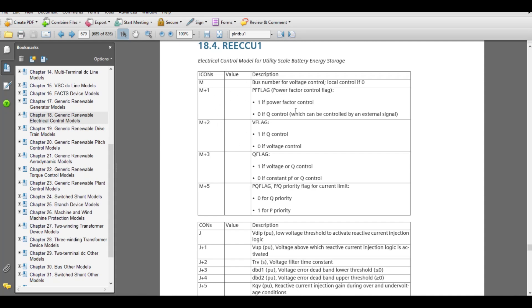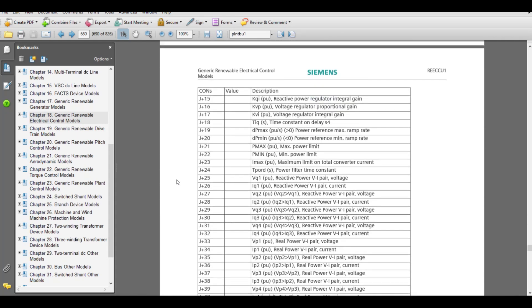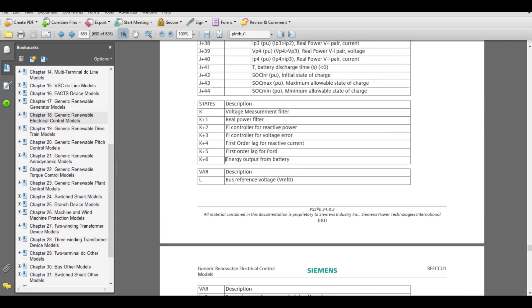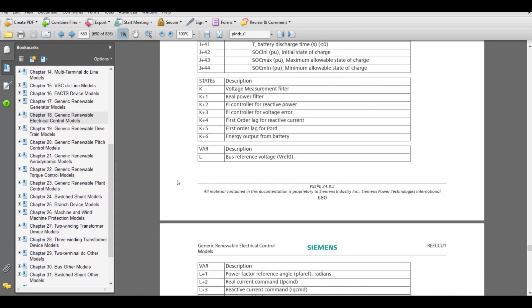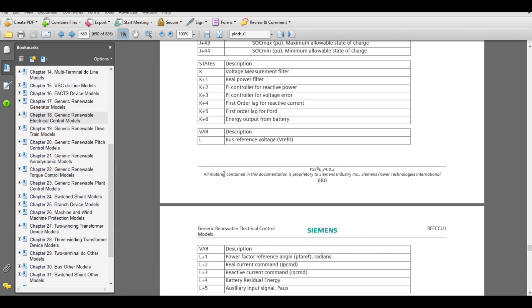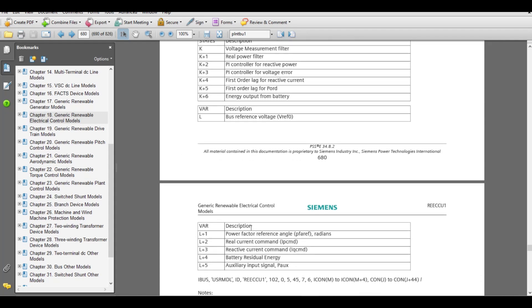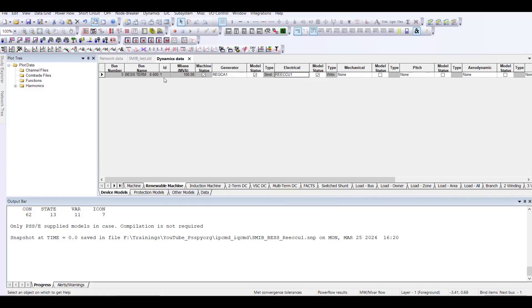If you go into that PDF file, you are going to find the model details — what kind of data you need to provide for the ICONs, similarly for the CONs, the states, and the vars. In PSSE, you can plot these states as well as vars. My area of interest is ipcmd and iqcmd, which correspond to L+2 and L+3 respectively.